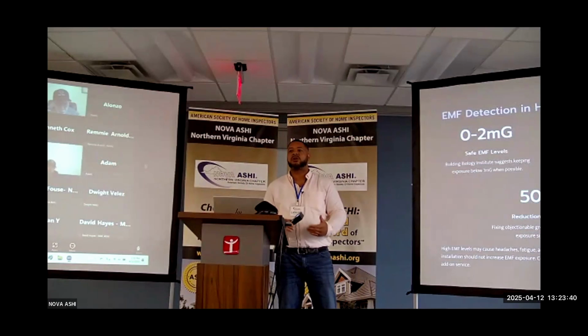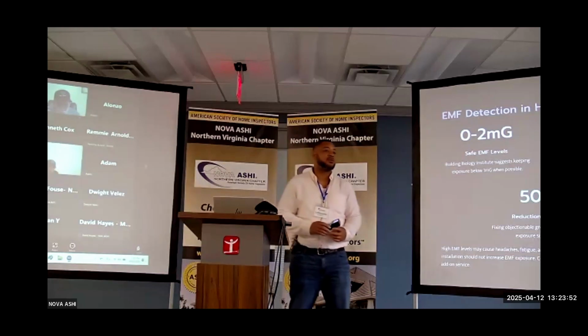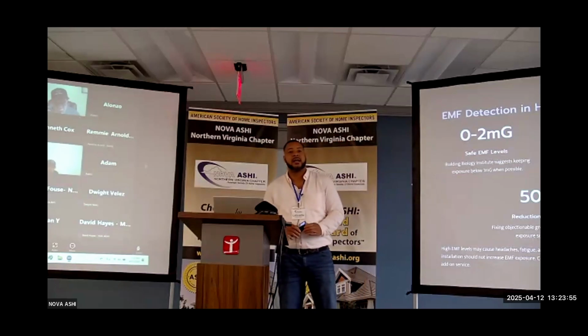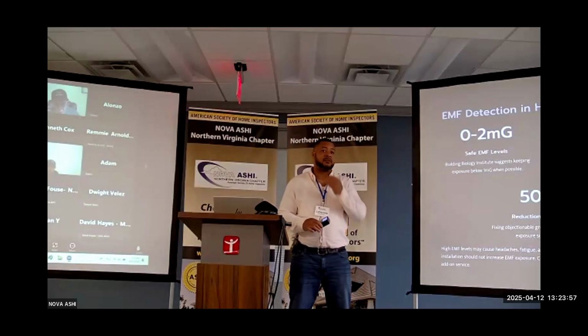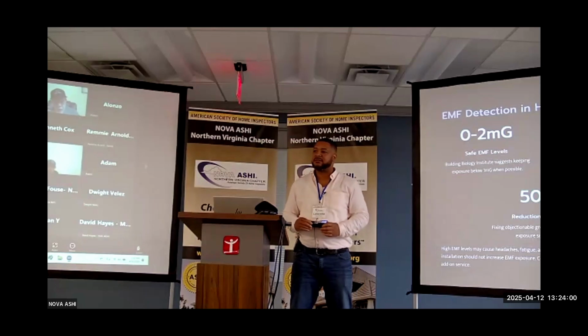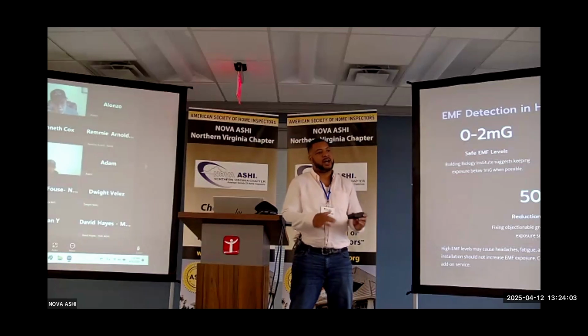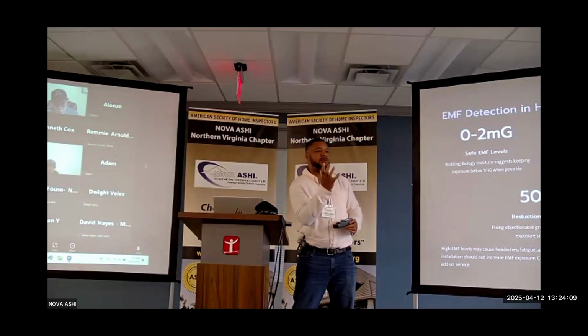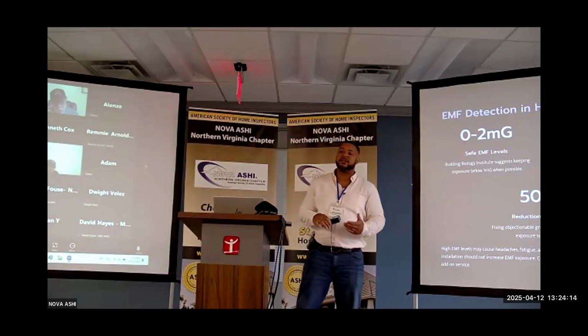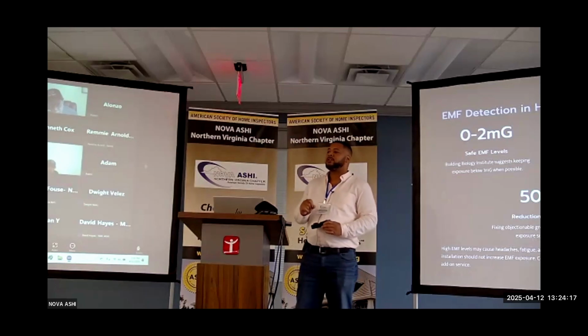We were able to troubleshoot and fix that. Another thing that actually causes this radiation is an obstructed ground, like ground faults and things of that nature. We found some in tight spots, like under cabinet lights, where someone may strip the wire and they've got the copper exposed, just a little nick, and they put a cover plate on there or something and it's touching the white wire. So you know what? It's not going to trip, and you're not going to know, because the neutral and the ground are bonded at the panel. They're like one at the panel, so you would not know.